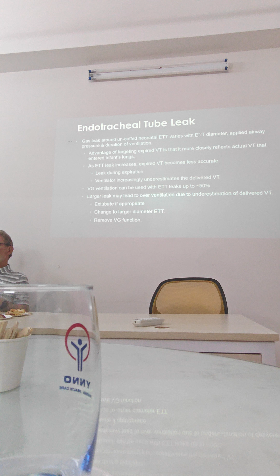However, in my experience, if you've got a really large leak and it's really affecting the baby's stability, and the baby isn't able to be extubated soon, I think there is big advantage in changing the ET tube to the next size up. The other thing people do is they remove the volume guarantee function and just go back to a set pressure. The disadvantage of that is that you've got no idea what tidal volumes you're delivering. They can be high, they can be low, they can constantly change. And so you've lost all the benefits of volume guarantee.